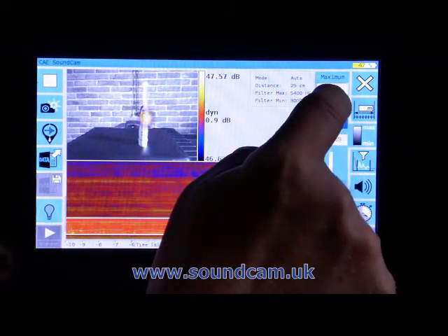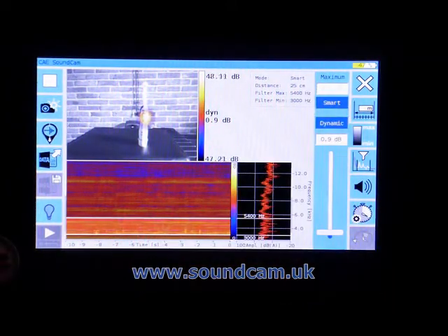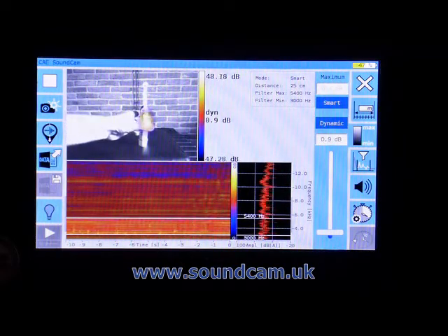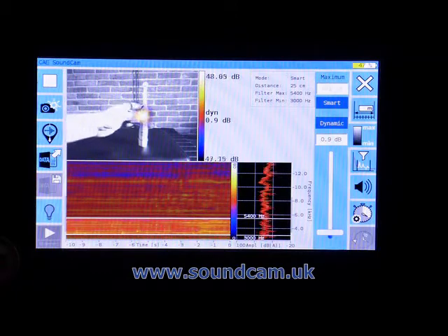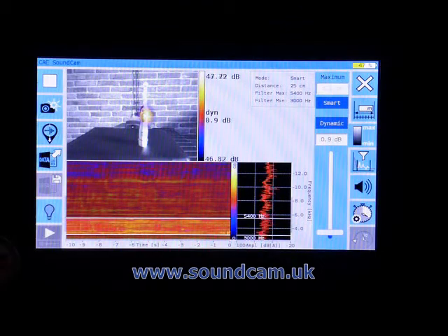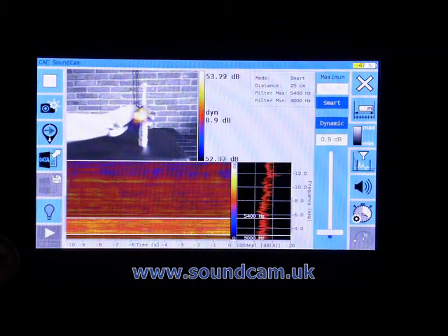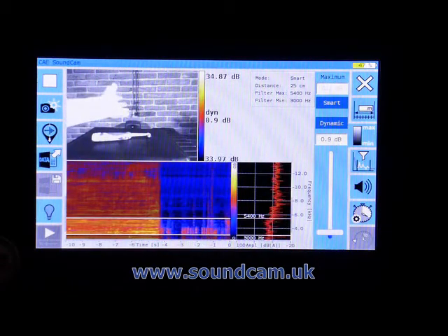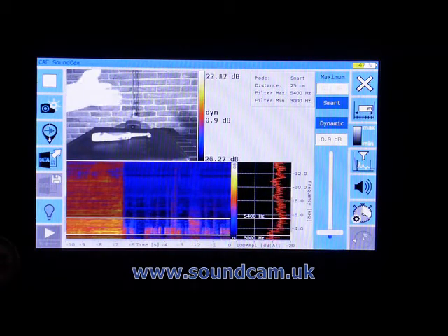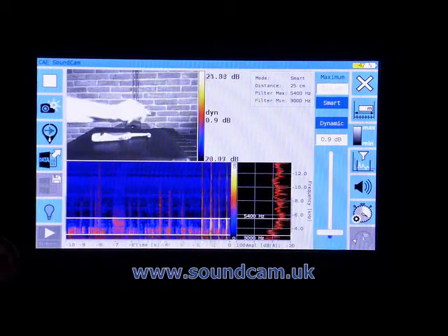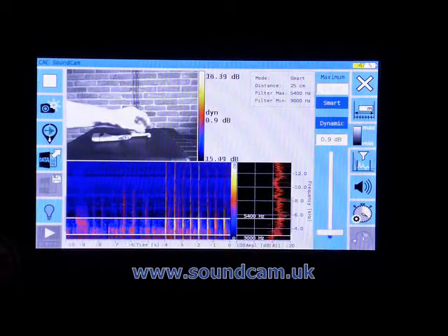If I press the upper button, the blue button here, I get to smart scaling. Now smart scaling is ignoring constant noises. Okay, some are more constant than others. This is sort of a rat-a-tat-a-tee one. It probably would ignore the higher frequencies better, but if you had, say, an air conditioning noise, if it was a fan going all the time, it would ignore that constant noise and average that away, and only look for transients that come and go over a particular amount of time.